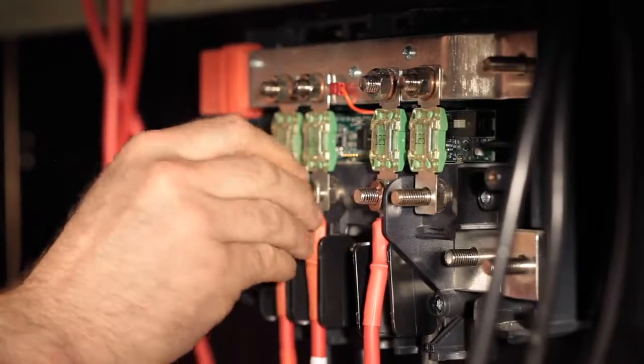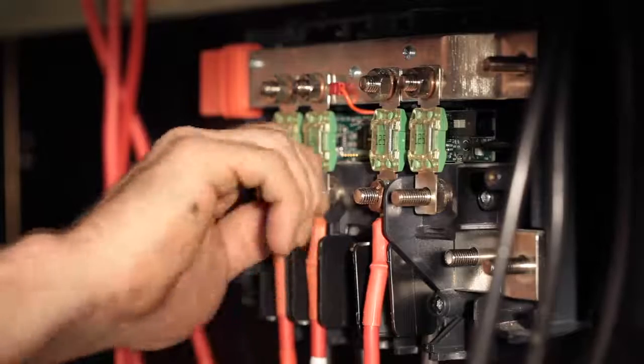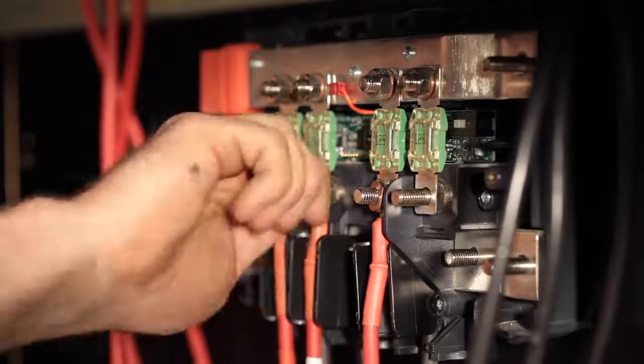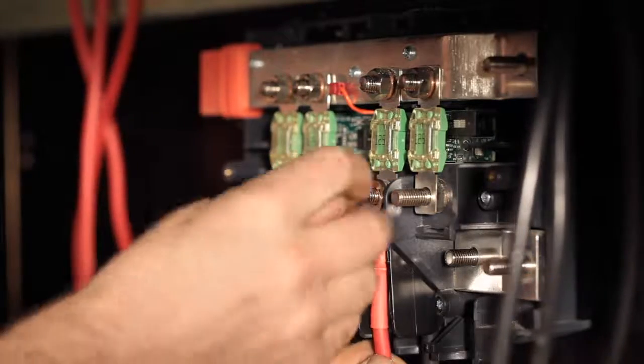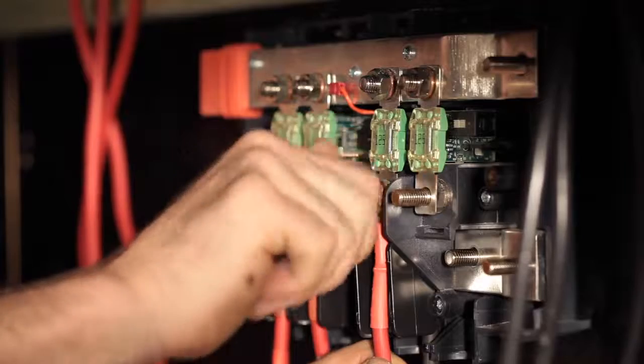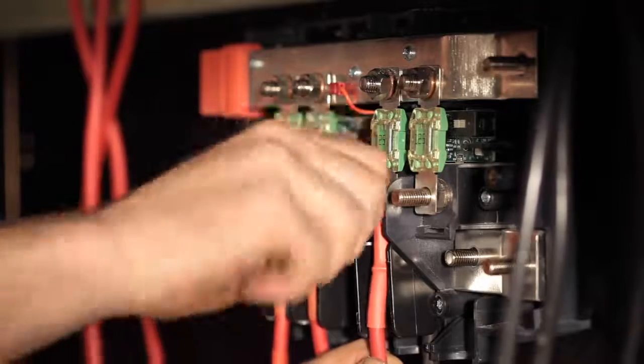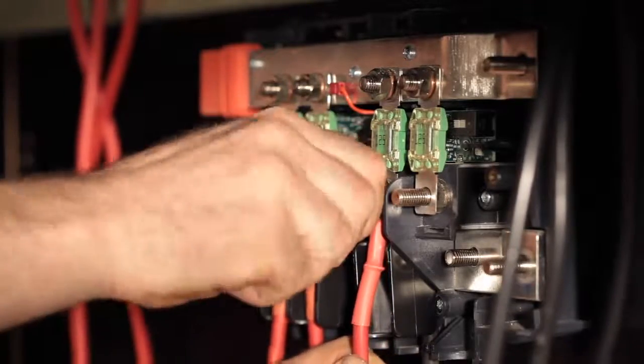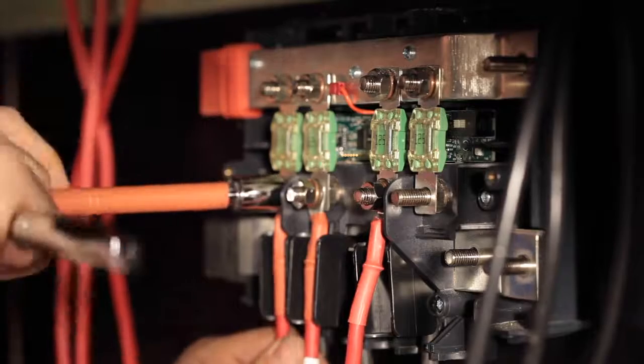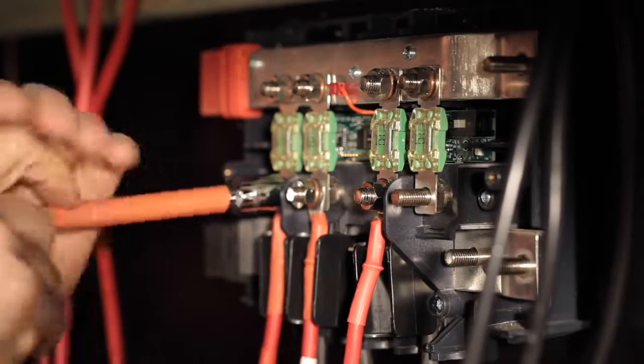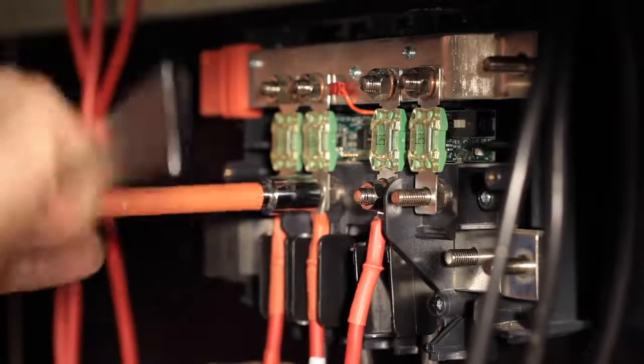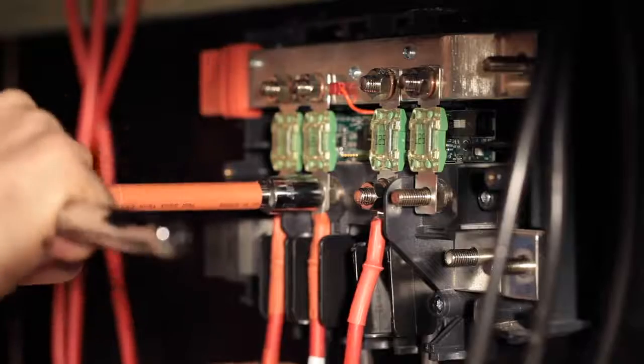Remember, these cables are also protected and isolated with the DC isolators up at the top of the cables before they enter the inverter. So in this case, they're double fused. This is for convenience as much as safety, but make sure that the cables are appropriately rated for the types of fuses that you've got.